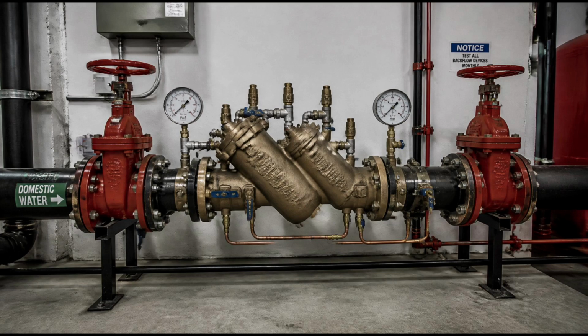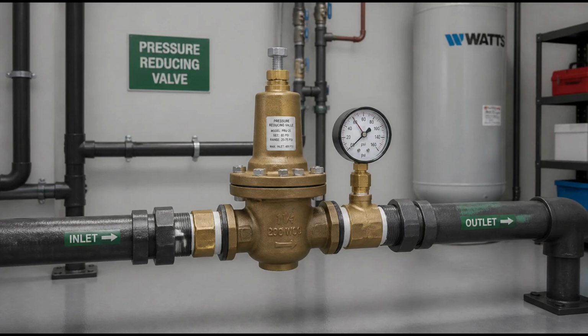The RPZ is a carefully engineered device that uses a combination of check valves and a relief chamber to maintain a zone of lower pressure between the building's supply and the city main. Under normal conditions, water flows through freely in the correct direction. But if conditions change, if building pressure rises above supply pressure, or if either check valve begins to fail, the relief port in the center of the assembly opens and discharges water outward, preventing any backward contamination. It is a system designed with redundancy in mind, because the consequences of failure are too significant to leave to a single point of protection.